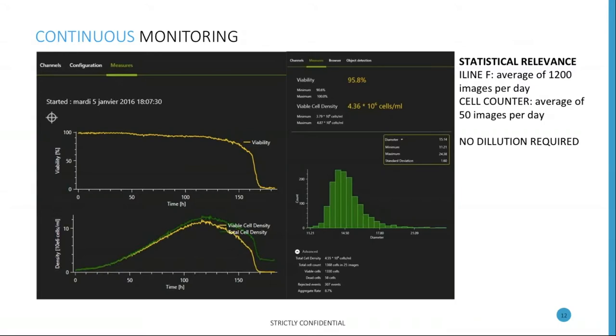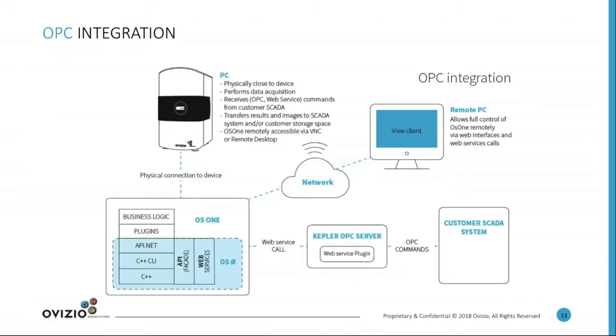On top of that, we do not require any dilution up to certain cell densities, which helps eliminate dilution bias and observer bias. The viability and viable cell density graphs are generated automatically. All this is done in software that is OPC-ready and can be connected to other devices or controllers to create feedback loops, or to automatically upload and update databases where you track all your culture.